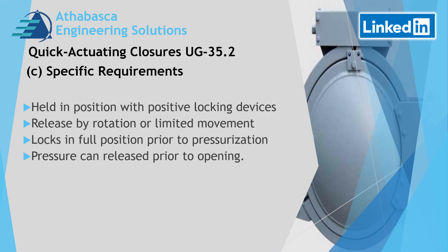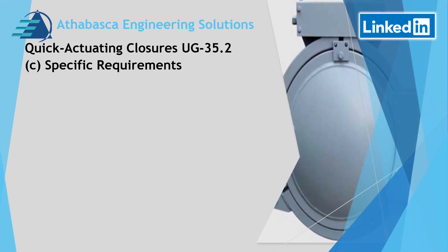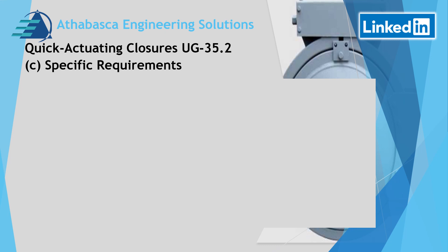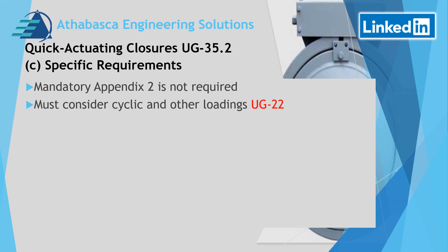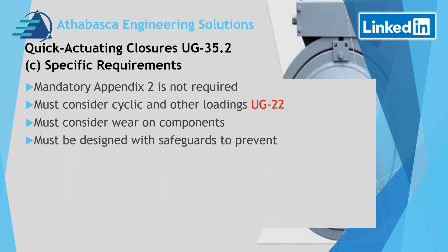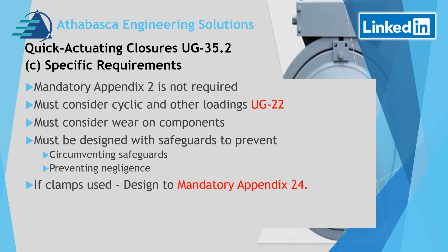The pressure can be released prior to opening. Part C — specific requirements: Mandatory Appendix 2 is not a requirement for this design. One must consider cyclic and other loadings as defined in UG22, as well as wear on the components. The design must include safeguards to prevent circumventing safety devices and prevent negligence. If clamps are used, then Mandatory Appendix 24 is required.